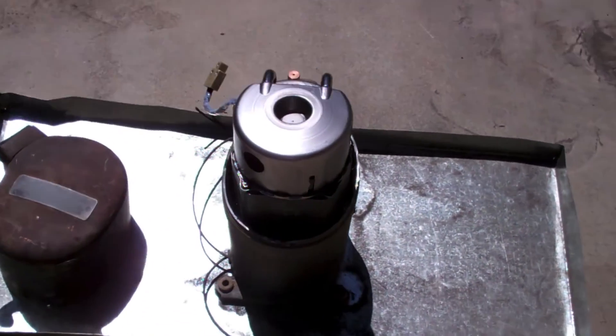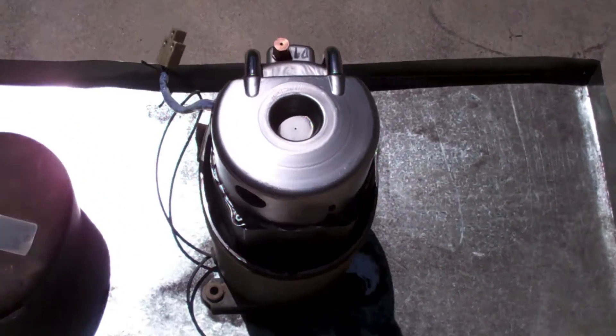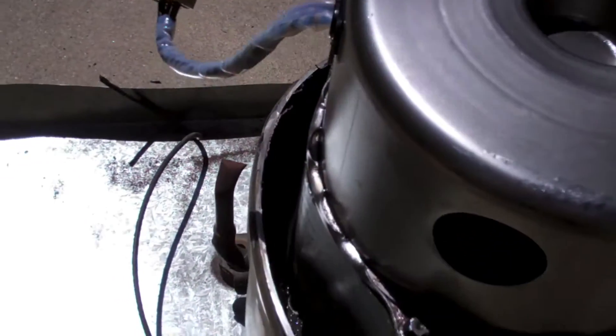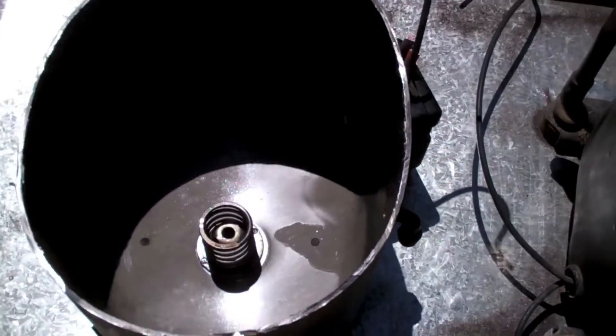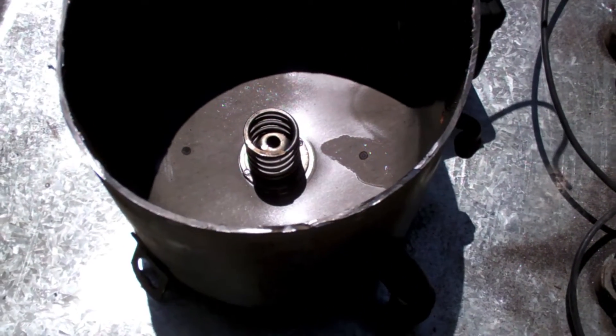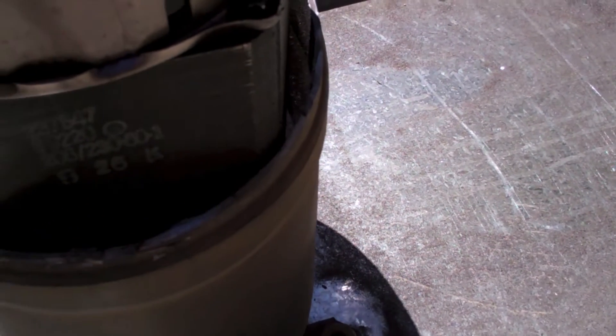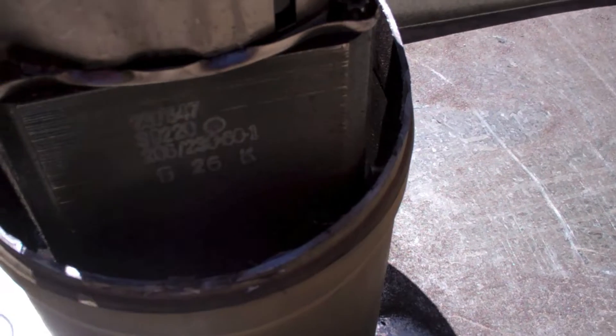It's all opened up, it's pretty clean. Again, this hole here is for the motor mount. See the motor mount and that's the top of the compressor. If you ever have a broken motor mount, this will roll up against the side and knock. I don't know if anybody's ever heard that before.